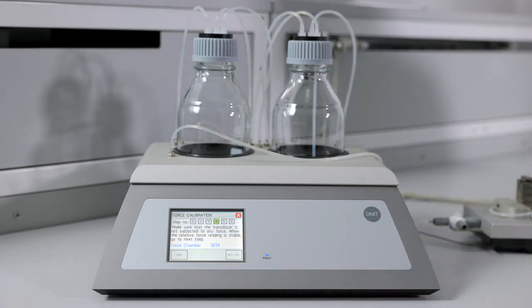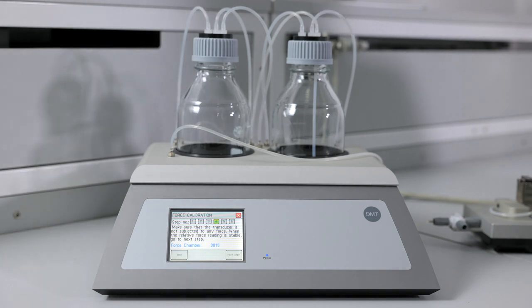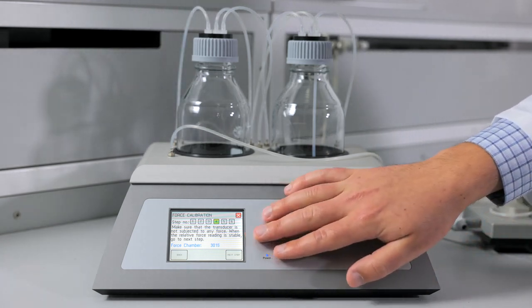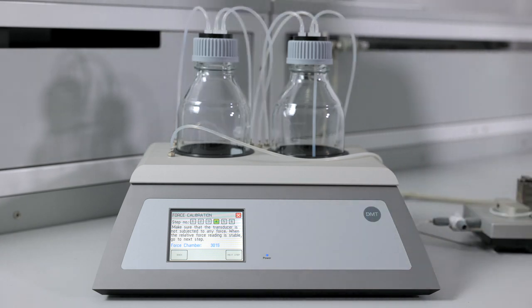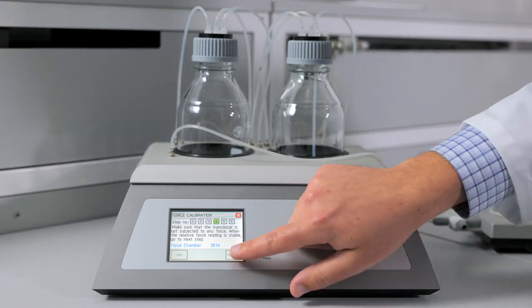Step 4 asks you to make sure that the force transducer is not subjected to any force. You want this number to be steady or going back and forth between two numbers. If that number is drifting in one direction or the other, it means that the force transducer is being subjected to a force. Recheck the position of your calibration bridge and then click next step.